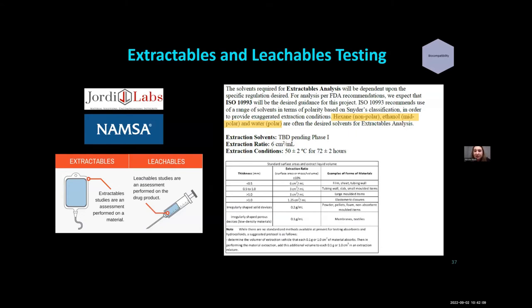There's also other testing you have to do on the materials called extractables and leachables. In addition to the more standard tests the FDA requires, as part of ISO 10993 they also require extractables and leachables testing, whereby you put your device in three different solvents, a nonpolar, a polar, and a midpolar solvent, and see what chemicals come out of that device. Then you can quantify how much of these different materials come out and whether they're at toxic levels in the device.